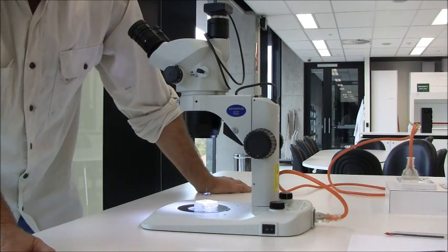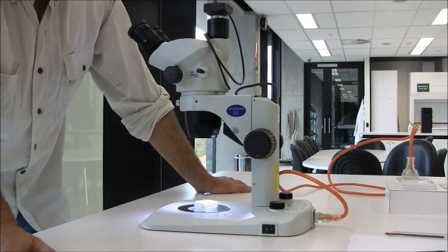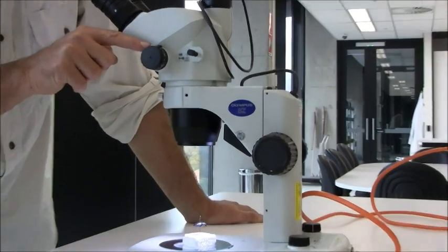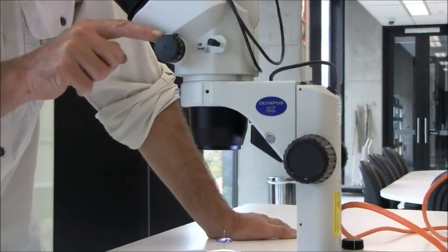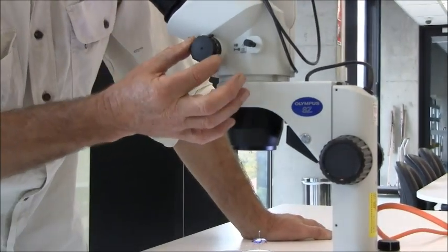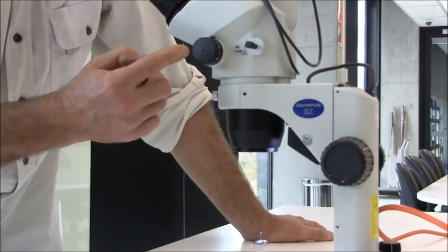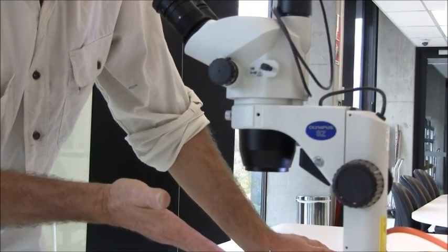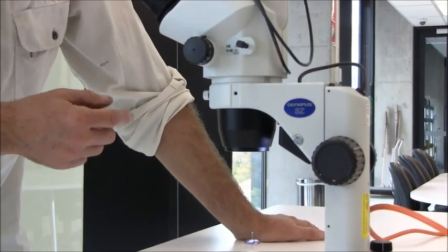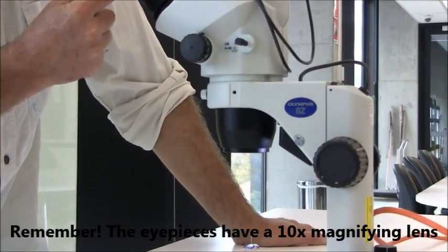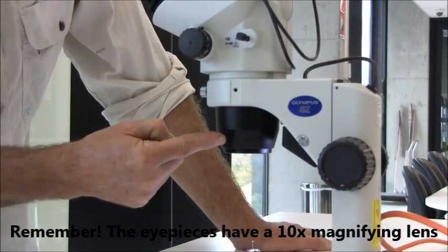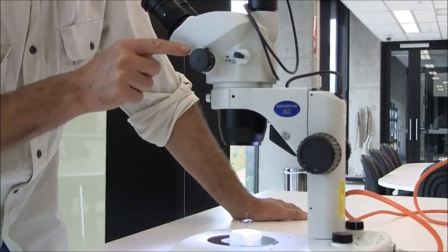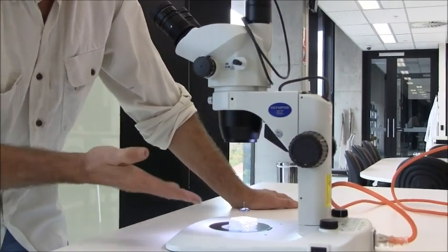These are quite simple. The last control I want to show you is the magnification, which is generally set at its lowest value, 0.67, before you start. We're currently magnifying this specimen at 6.7 times, because the eyepiece is 10x and the objective lens, controlled by this knob, is 0.67. Ten times 0.67 is 6.7.